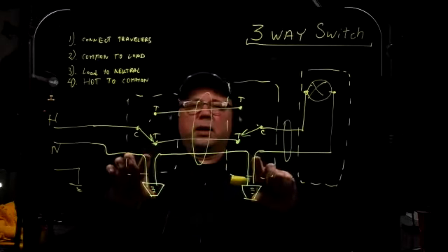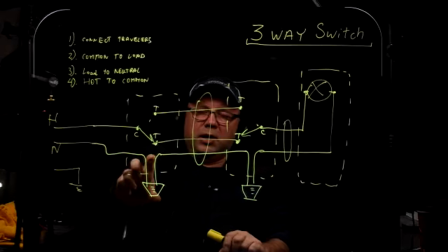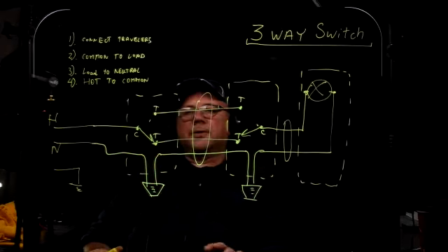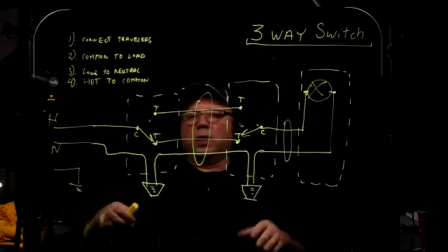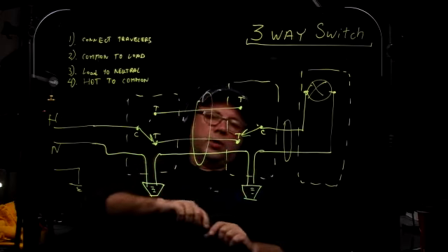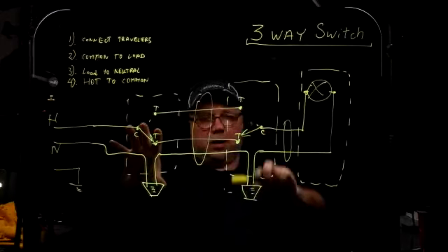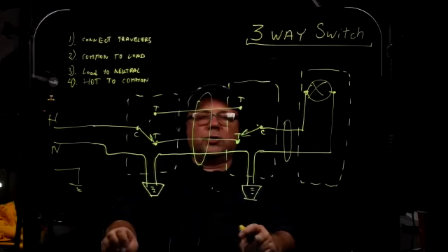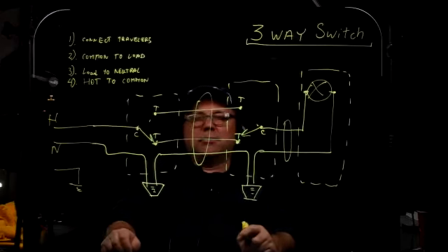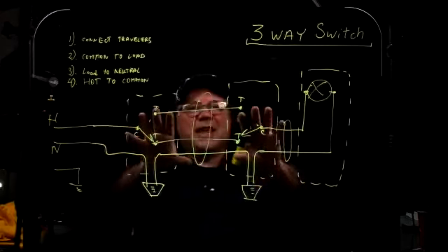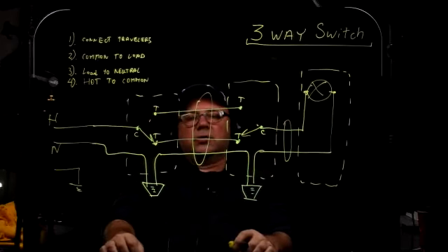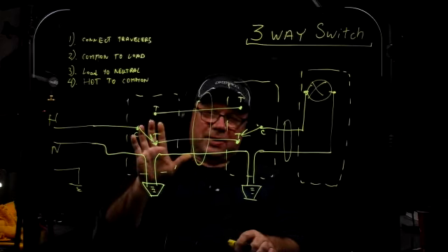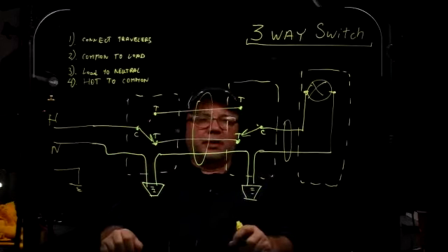So that's why I'm going to ask you to actually make the pigtails, and we learned how to make the pigtails last time. Right? So it's all kind of falling together as we go along, and I'm going to show you how to make proper wire dressing inside the device boxes, so you're not creating some sort of a bad haircut mess in the boxes, and then you're going to have control over actually compacting all those wires inside the device boxes.